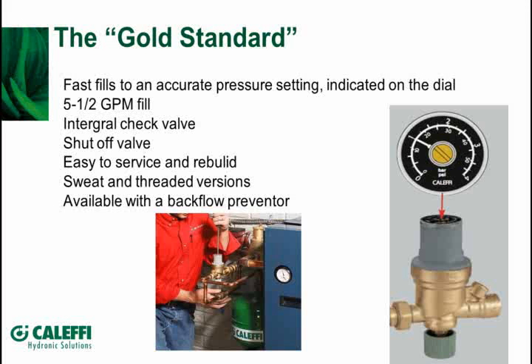So if there's one valve that's probably my favorite valve of everything Caleffi makes, I would say it's our autofill valve. I'm calling it the gold standard because there's none other like it. It's very unique and very user-friendly. The first thing I like about it is on the very top, you can take a screwdriver or the edge of a coin, a quarter or a penny, and set the pressure that you're going to fill your system to. Let's say you're going to fill your system to 15 PSI. You just set that at 15 pounds pressure, and that's all you have to do with this valve. It's as accurate, in fact more accurate, than a lot of the gauges that are shipped on the boilers these days. So if you know you want 15 pounds, set it to 15 pounds, and it's going to maintain that pressure.